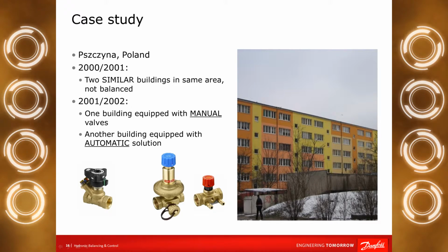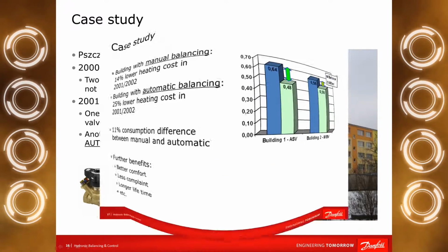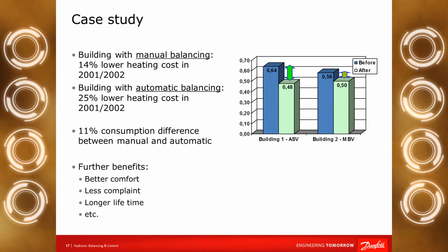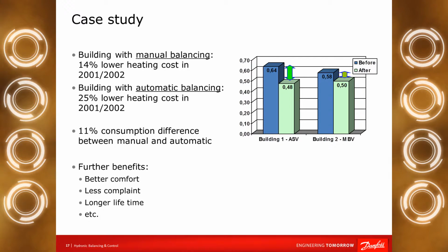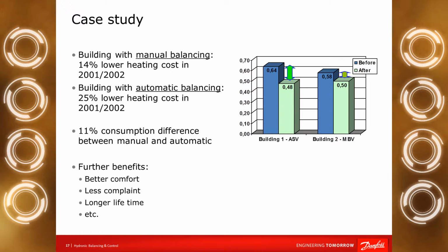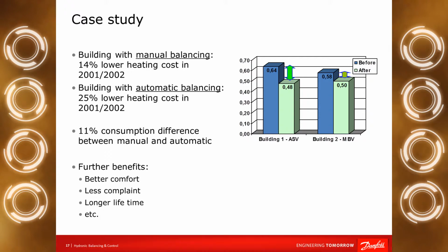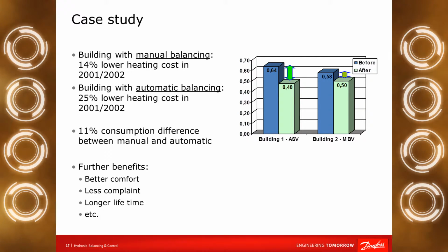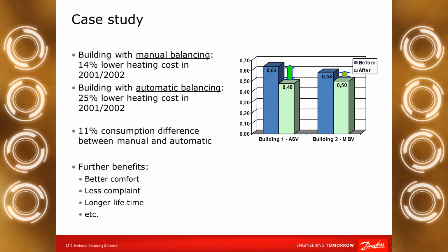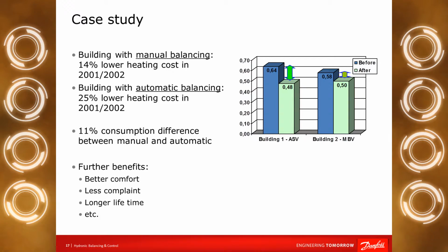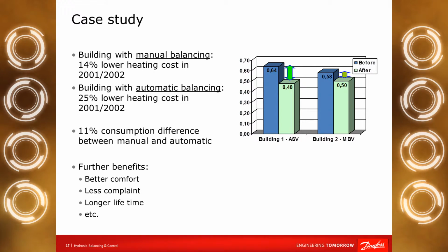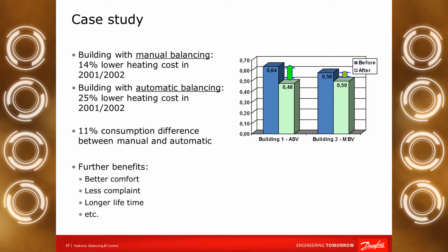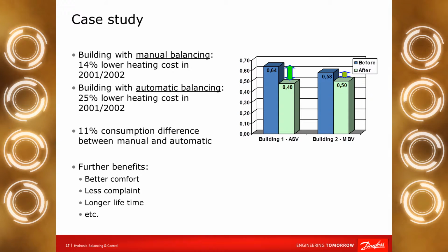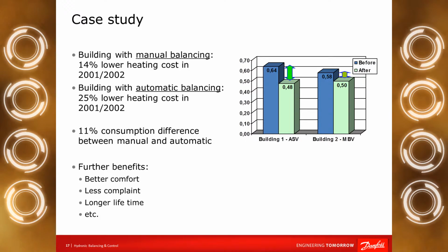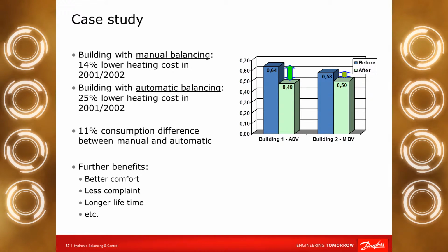After a year, we measured what the energy consumption difference was before the renovation and after the renovation. We experienced that the energy saving potential based on usage of automatic balancing is huge, because the saving difference after the renovation was 11%. That means if we don't use any balancing in the system, probably we have around 14% more energy usage. If we use automatic balancing, the energy saving potential is 25%. The difference between them is 11%. So very close to the previously shown energy saving potential on a theoretical level. It is proved in reality based on the real measurement.